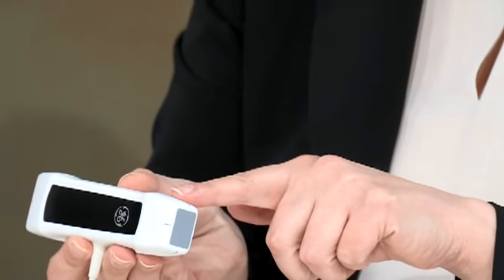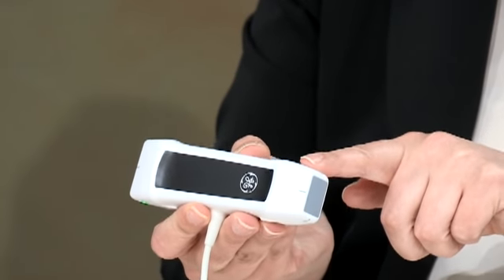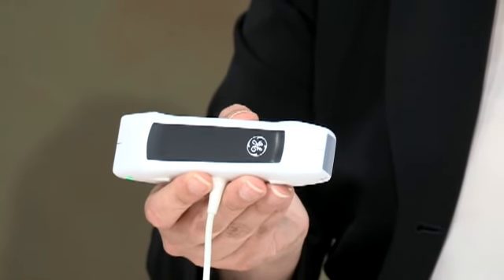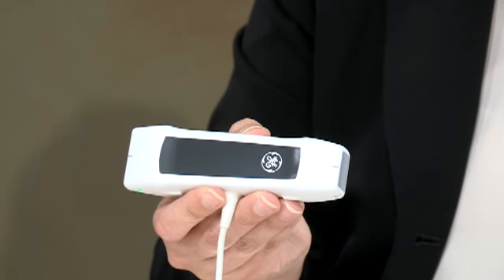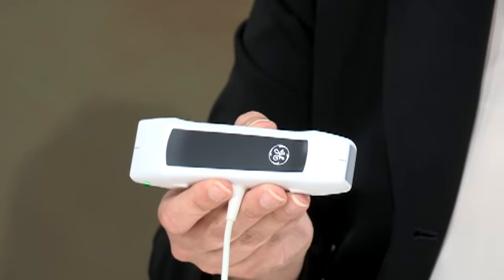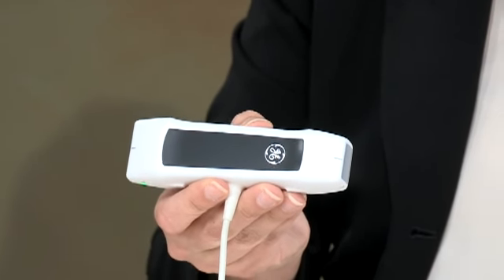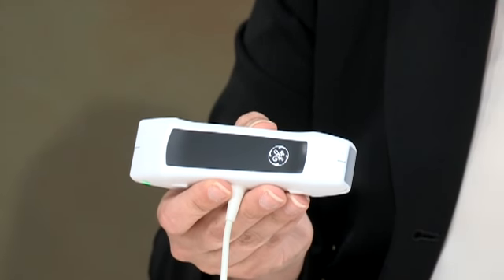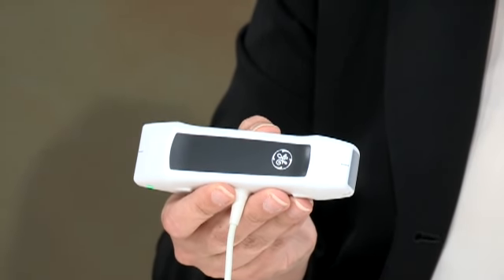The Vscan with Dual Probe is the first of its kind single probe solution supporting two transducers. Here you'll see we have the deep or the phased array ultrasound transducer. The deep probe provides an imaging frequency between 1.8 and 3.8 megahertz. The depth for the scanning for the phased array is between 6 and 24 centimeters.